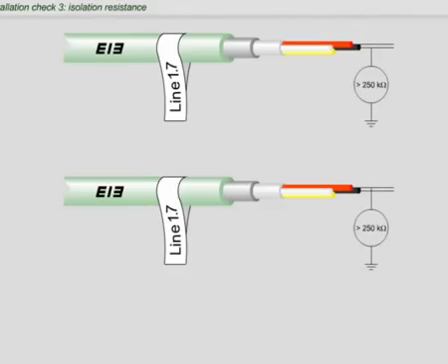As the EIB operates as a SELV circuit, the isolation resistance of the bus cable should be measured. All overvoltage arrestor terminals must be removed before carrying out the test. The test results should be added to the documents of the EIB installation.